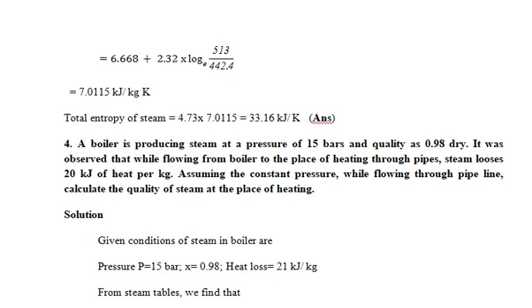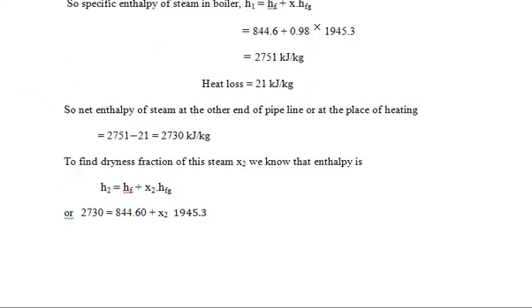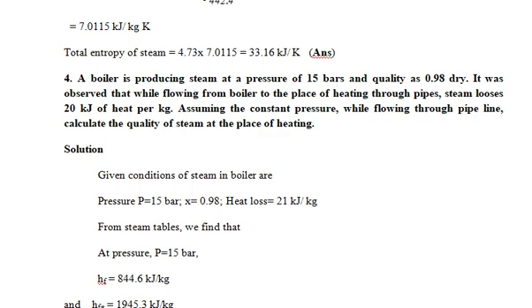The boiler is generating steam at 15 bar with dryness fraction 0.98. When the steam flows through the pipes to the heating location, 20 kJ per kilogram of heat is rejected by the steam. Assuming constant pressure, you must determine the quality (dryness fraction) of the steam at the place of heating. From the steam table at 15 bar, find hf and hfg. Calculate initial enthalpy H1 = hf + x·hfg. Substituting values, H1 = 2730 kJ/kg. Then the net enthalpy at the other end of the pipe (at the place of heating) = H1 − 20 = 2710 kJ/kg. From this, find the new dryness fraction.